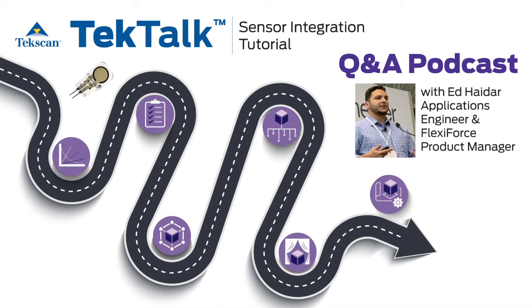So what should guide you towards whether you're using a square wave or a DC signal would be: what type of measurement resolution do you need? What sensitivity do you need? Can you make the lower voltages work for you? Signal to noise ratio, things like that. And then if you do need the square wave, you could work with our applications team, based on your loading profile and the necessities of the application, to determine the optimum frequency for the square wave and the parameters of the supplied square wave itself.